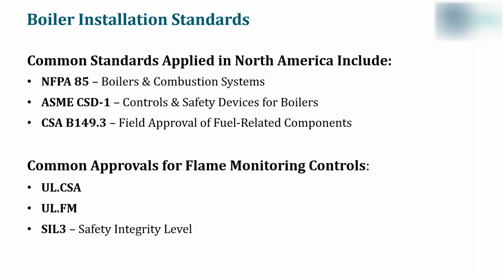Now this final one, not everyone may be familiar with. SIL is defined as a safety integrity level of equipment. And putting it simply, it's a measure of the performance that's required from a safety instrumented system, in this case the LMV, to maintain or achieve a safe state. You may recall how I mentioned Siemens has built a reputation on safety. Well, this ensures that the LMV will take the necessary measures to prevent a hazardous situation from developing. Additionally, a SIL rating is based on a scale of 1 to 4. The Siemens LMV system maintains a 3 rating.